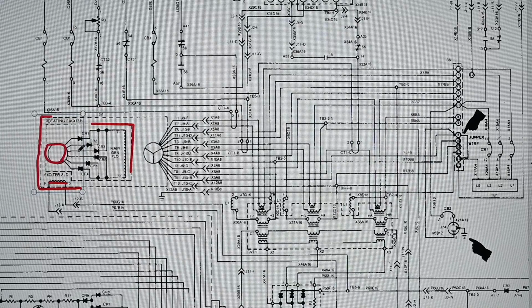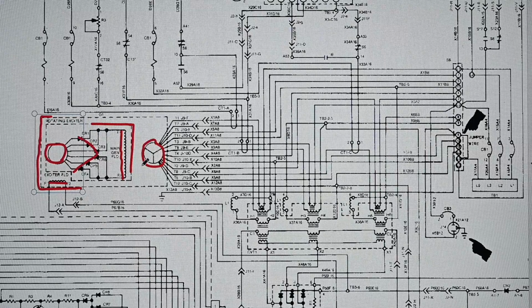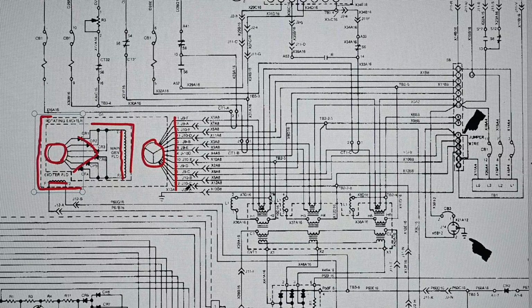And this 3-phase voltage is rectified by these 6 diodes. Okay, so you have a bridge rectifier, 3-phase bridge. And that creates a DC voltage on this main rotating field right here. Okay, so this field winding is spinning or rotating inside this stator winding. So this is a stationary winding, which is on the basically outside frame of the generator. And you can see that the voltage that's then created in the stator is brought out on these 12 wires right here. And I mentioned it's a 12-wire generator.